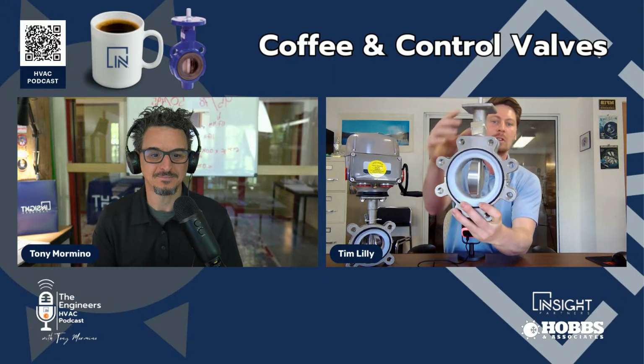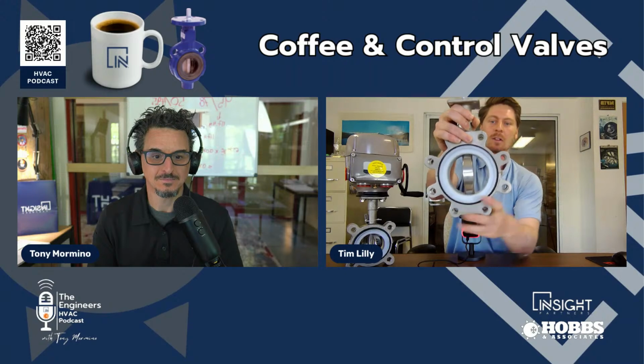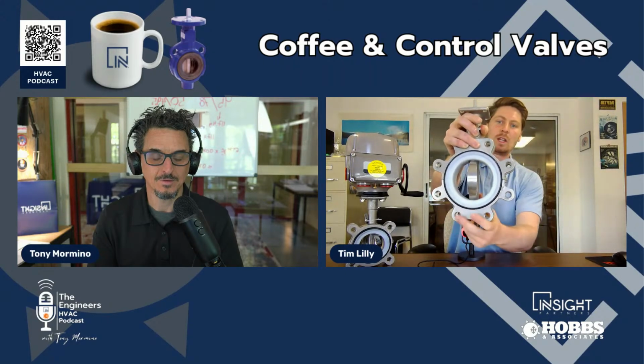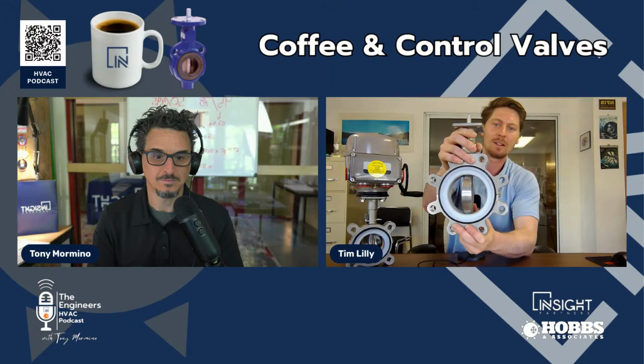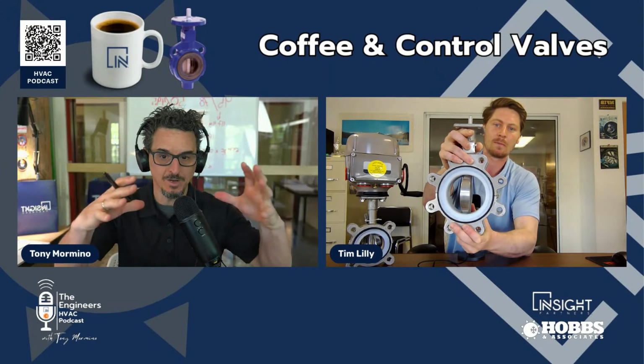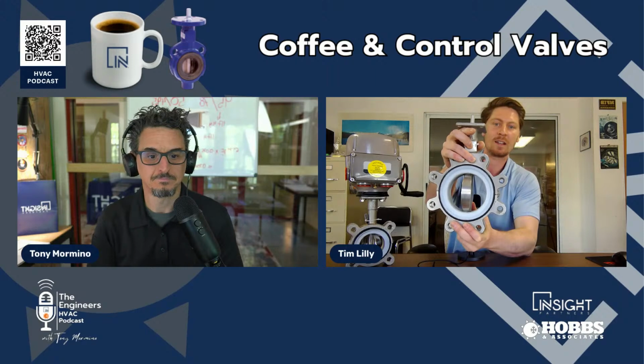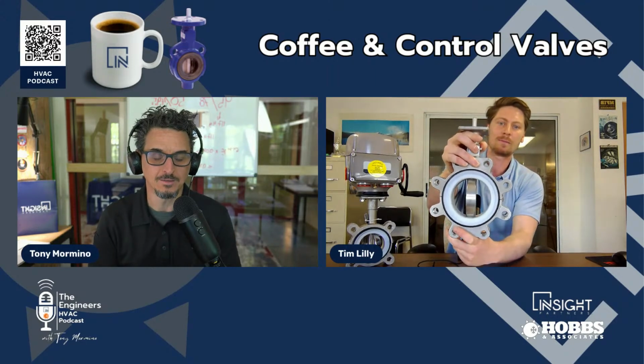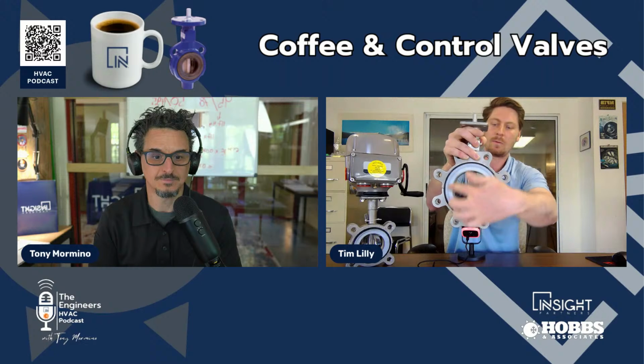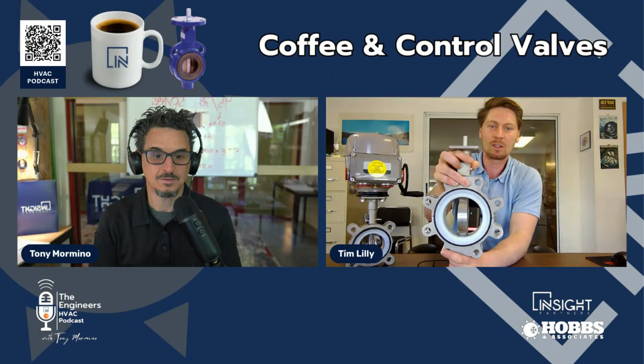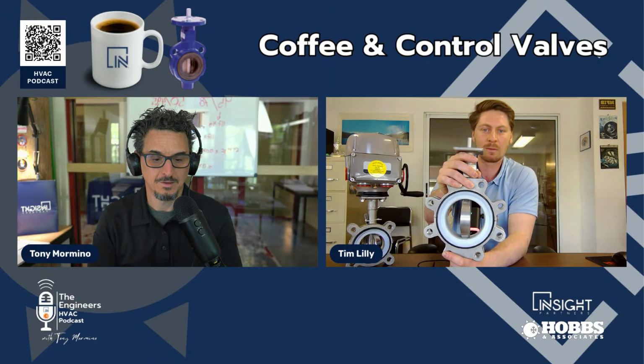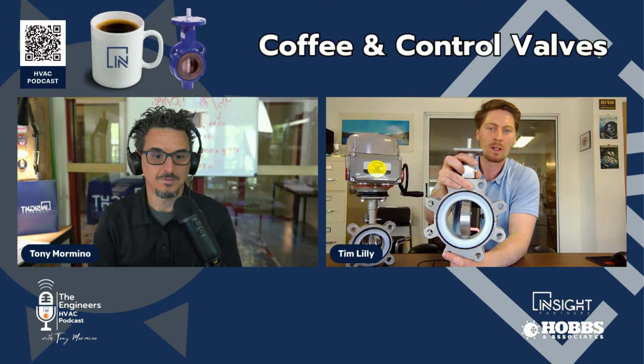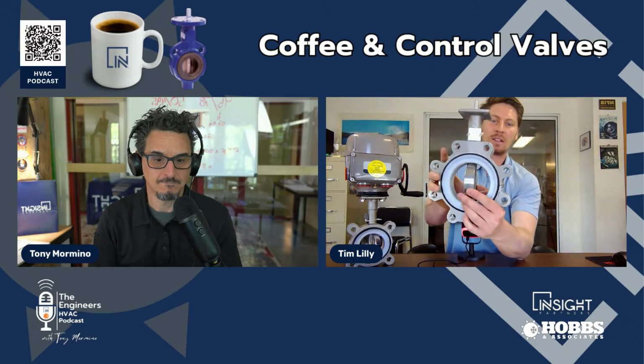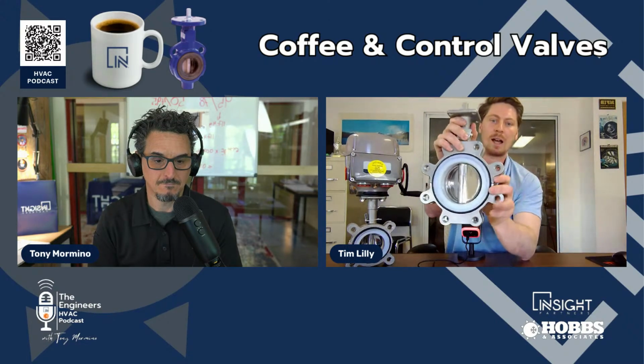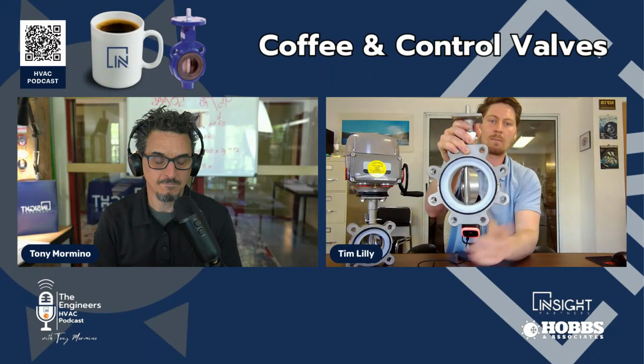Perfect. Okay. So this is a standard lugged style valve, which this is a lug. You can get it in a wafer, but that's kind of a European thing. So the lugs would be where the flanges of the pipe would come to, and you'd put a bolt through there. Yes. But those are called lugs in the valve world. Got it. And then this is your resilient seated liner. In your industry, they're all EPDM, which is just a rubber. And it basically makes it a soft seat, an O-ring seat. And then you have your disc, which in a standard butterfly valve just goes on and off. But with ours, we can modulate.